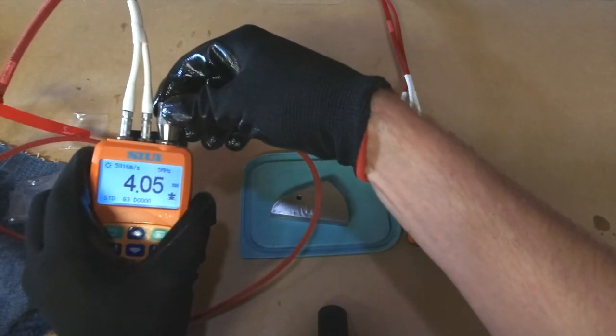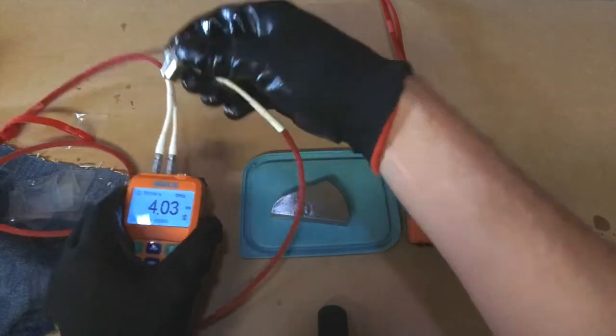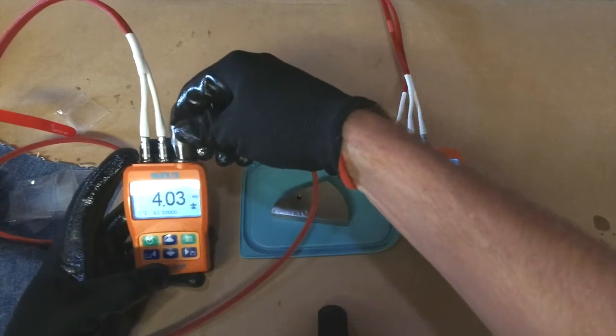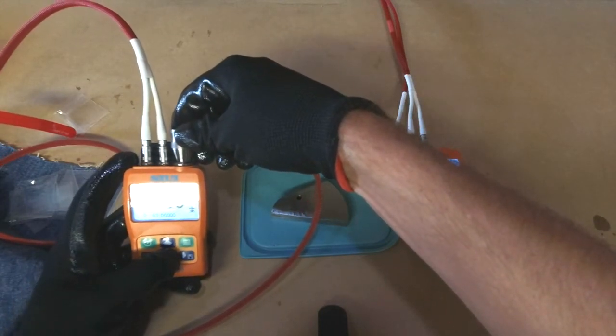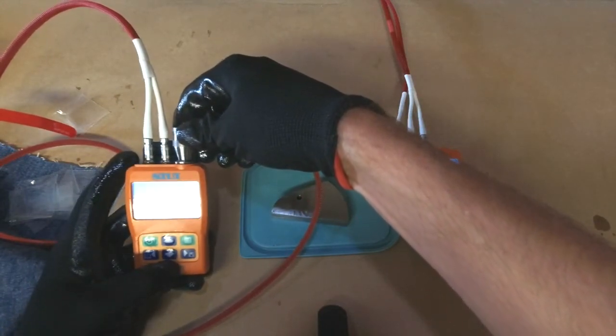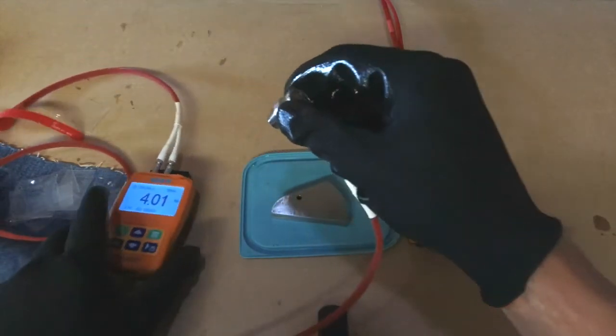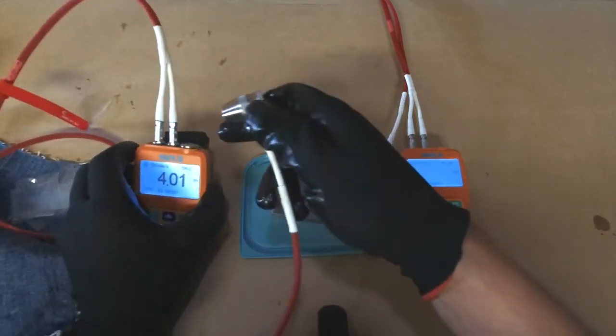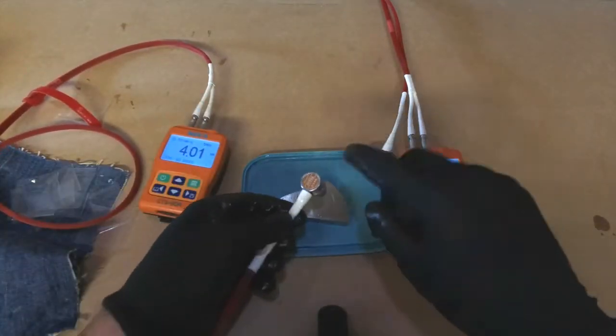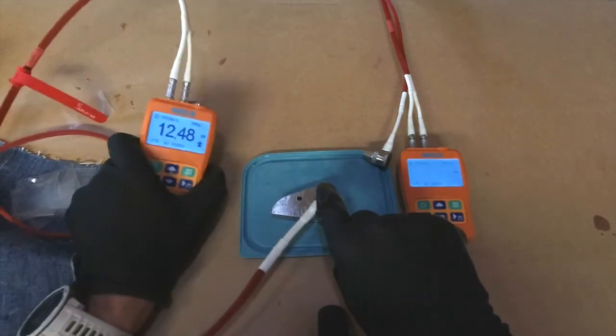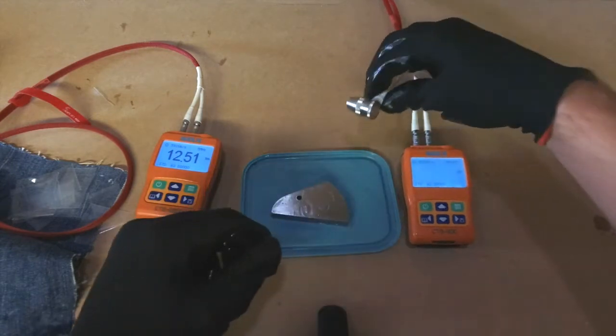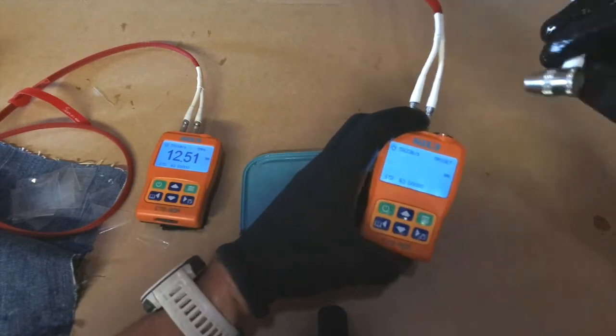So we know this block is a 4mm test block, but when it turns on it already understands that. But we'll also make an adjustment or a calibration, a self calibration. And we can see its adjustment is complete. There. And so the original material of this and this may be different, but let's see what this comes up with. Okay, that's not too bad. Not perfect. We'll do the same thing with this.